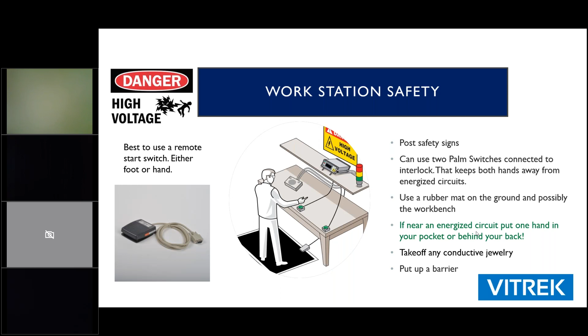These are safety enclosures, and they're a good idea. The way they work is the DUT goes inside the safety enclosure, and the tester and operator stay outside. This is metal - it is conductive, and the reason this makes you safer is because it's tied to ground, so if anything happens inside to cause a high voltage to touch that metal, it is fully grounded. It'll probably blow your fuse, hopefully, but if not, you'll be at 0 voltages if you touch that. You'll notice that little safety light on there - that's optional, you don't have to have it, but it can be wired up so whenever there's high voltages on, it turns red.